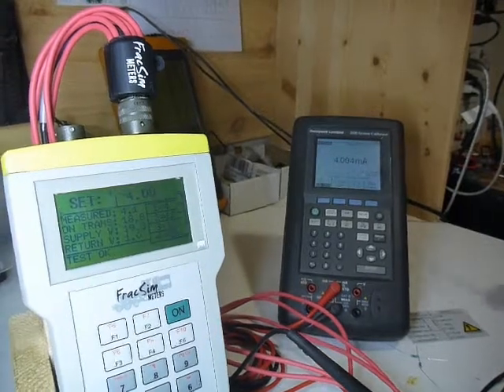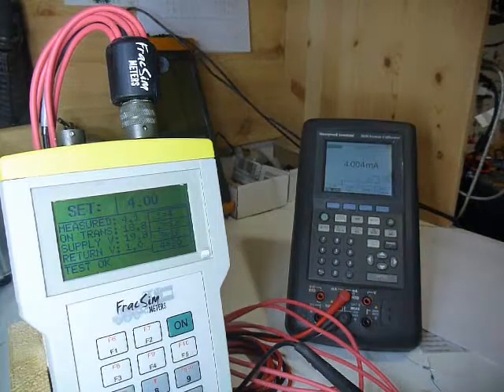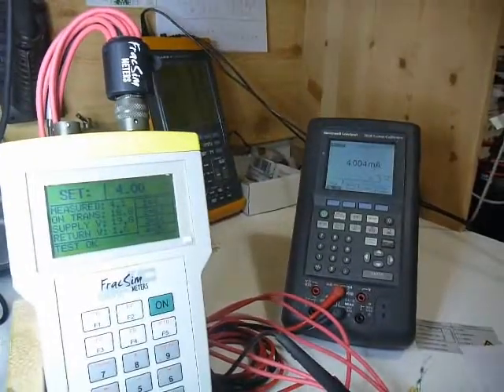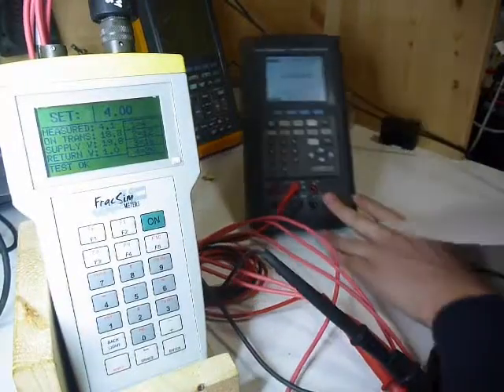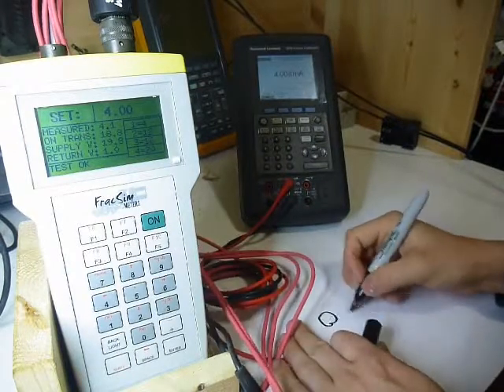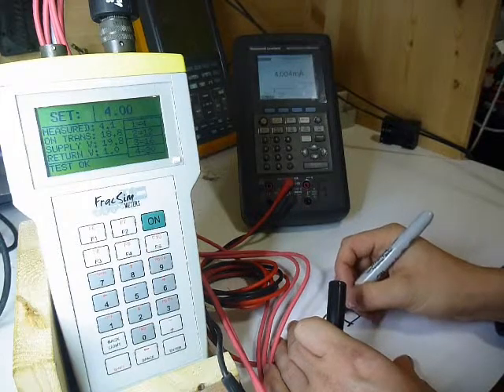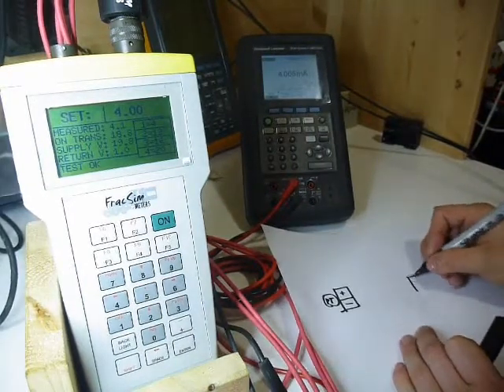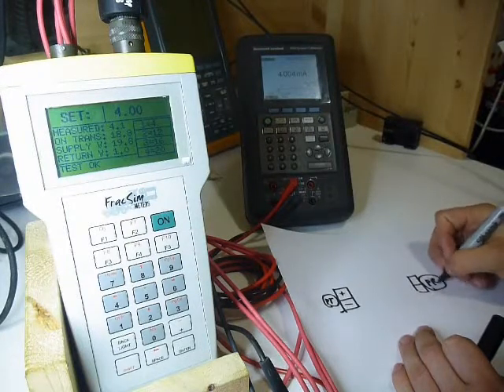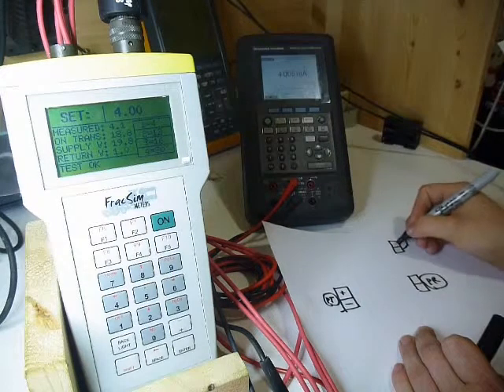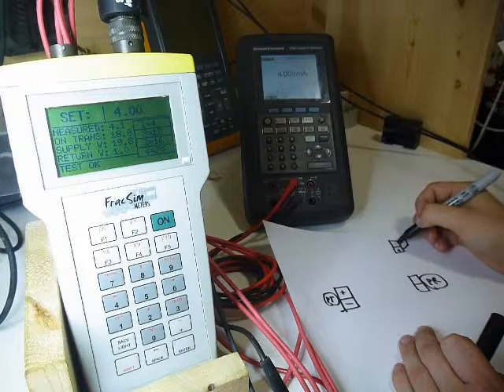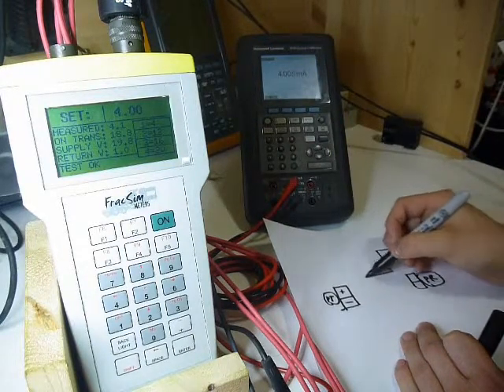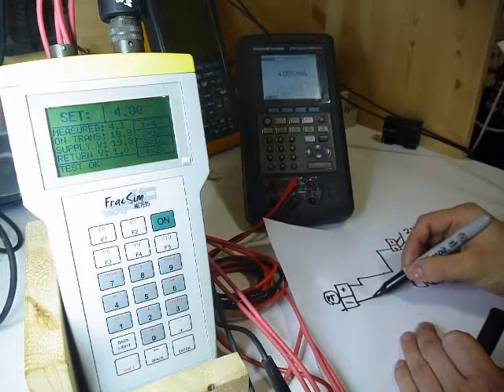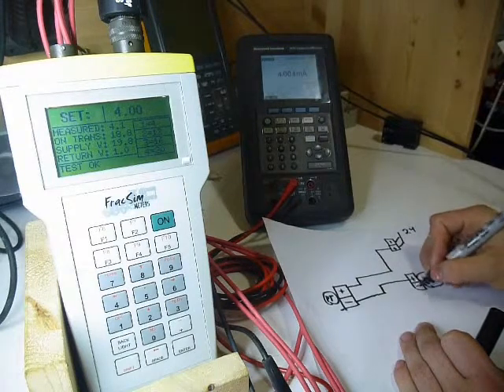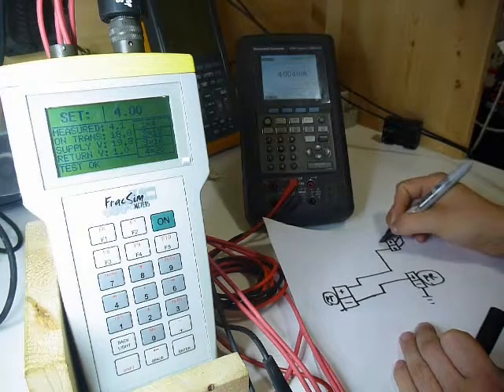If I were to quickly draw that out so you can see. Basically what you got is, we'll do the instrumentation type drawings. Pressure transmitter, and you got a pressure recorder and our 24 volts. So the loop actually looks like this. You got 24 volts coming out of here, going into your pressure transmitter, or Fracsim, whatever, returning back to your pressure recorder, and then of course going back to frame ground. This of course here is just frame ground.